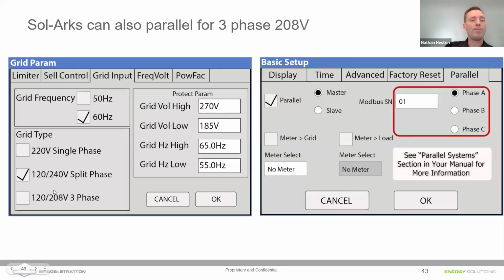And then if you want to have balanced 3-phase, you can use 3 inverters or combos of 3, 6, 9, or 12 inverters for balanced 3-phase. You can parallel up to 12 of these inverters, both in split phase or 3-phase configurations.